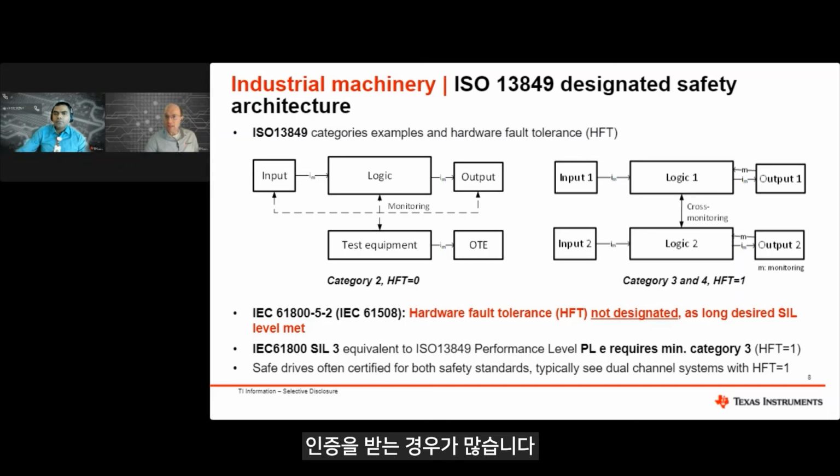MCU-based solutions also allow setting the torque command to 0. Electronic solutions typically allow faster response time to STO as well as faster recovery from STO, and are also typically more reliable versus mechanical solutions.